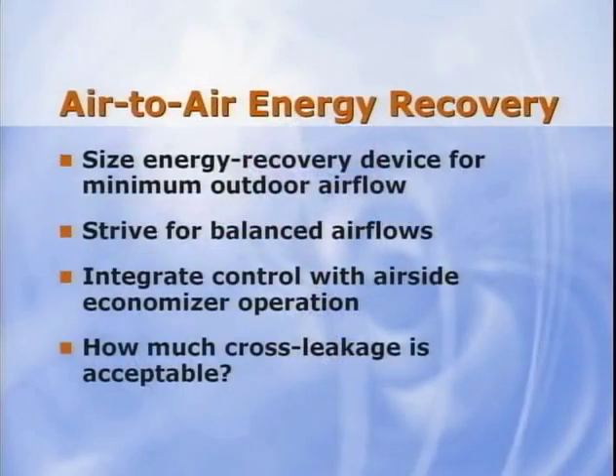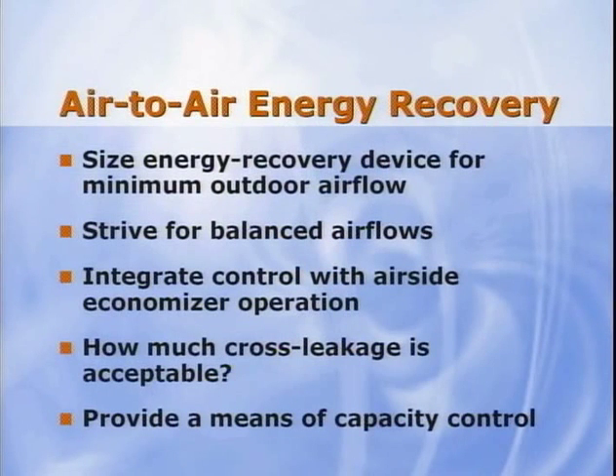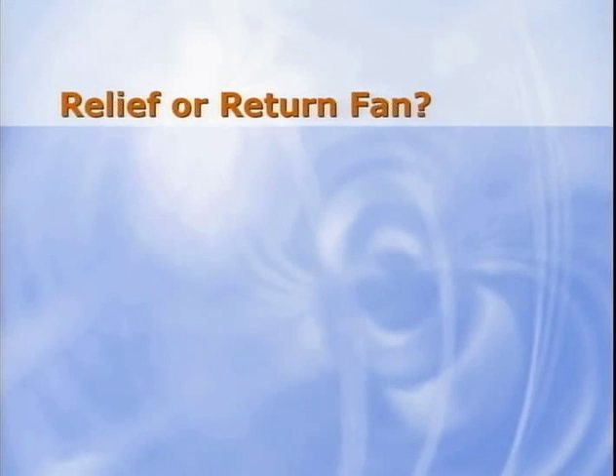Finally, provide a means to control the capacity of the energy recovery device. During cooler weather, VAV systems may require a means to modulate the capacity of the wheel to avoid overheating the air. Next topic, relief or return fan. Economizer operation must include maintaining space pressure. It's important to remember that a properly pressurized building will be the most comfortable, not just the most economical and the least problematic.